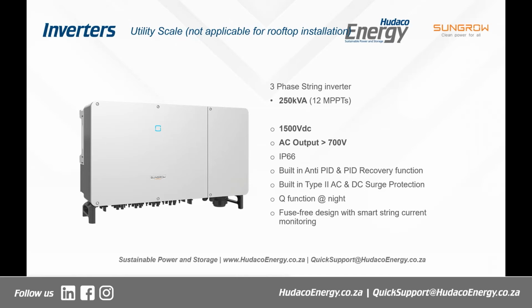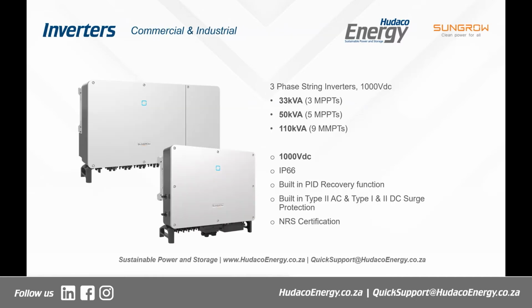Okay, let's go to the products which are now much more applicable for a rooftop application, and this is the 400 volt PV inverter range. Next slide, please. In this range, we have the 33, the 50, and the 110 kVA unit, each with a different amount of MPPTs coming in. These are 1,000 volts on the DC side, which means you can absolutely install them. You don't have to worry about building code irregularities, as long as it's installed properly, obviously.